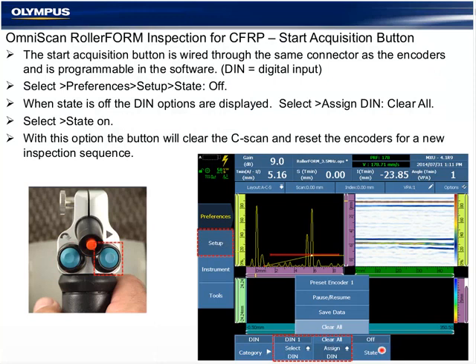When the state is off, the options appear for the DIN, and there are several of them. DIN 1 is the only one that's wired to the RollerFORM. Any of these options are available, but the one that's defaulted in the setup files that are provided, and the most useful for day-to-day operation, is Clear All. When I click this button, based on my configuration here, it's going to clear the C-scan data and set both encoders back to 0, indicating I'm ready for a new inspection. We do that just after repositioning the scanner correctly.